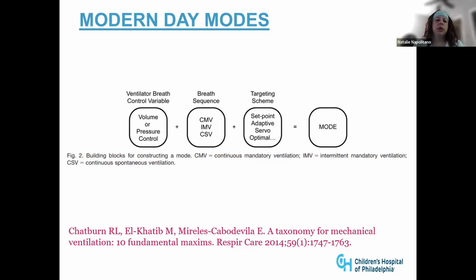And that's how people should really think about it and say, I want a mode. If you don't know what the device is, but you know what you want for the patient, it's: I want a pressure controlled mode that the patient can breathe on their own, but I want to target tidal volume, or I want to target minute ventilation, or I want a volume mode that targets volume. It's very different than we have a pressure mode that targets volume, which oftentimes have a volume name in them.